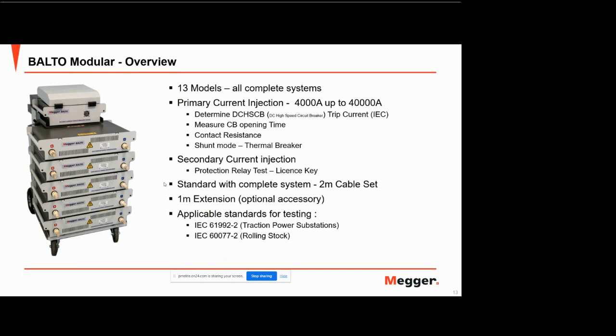So those are the main primary current injection tests. Balto also has a secondary current injection. This is where you're testing your protection relay. So this is an optional extra. Not all customers necessarily want to test the protection relay, but it's there, it's available, and you can actually test your secondary current injection. And typically what Balto does, it simulates the output of your shunt into the relay. So you can actually output low voltage to simulate the actual output of the shunt for live line conditions.